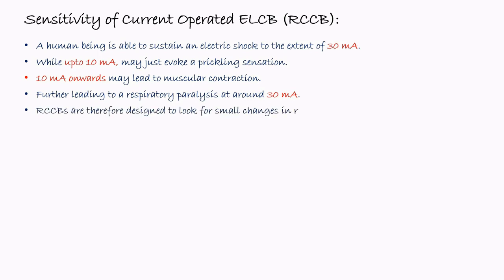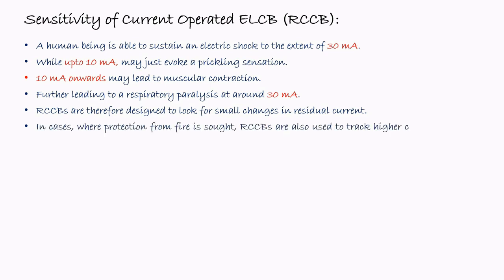So RCCBs are therefore designed to look for small changes in the residual current. So it is very important to protect human beings as well as other animals from electrical shock. In case where protection from fire is sought, RCCBs are also used to track the higher change in residual current, up to 300 milliampere. So this is also possible in case of RCCB.